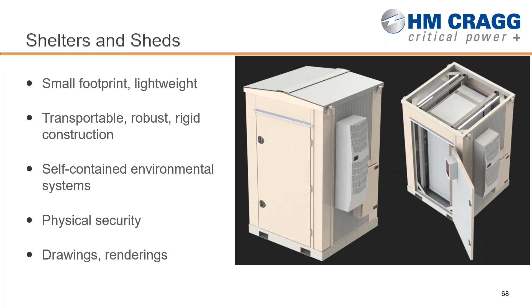Here's another example where we had everything in one cabinet: UPS, battery cabinet, automatic transfer switch, custom input and output distribution so we could plug in pin and sleeve, and redundant air conditioners built in, with Conex style doors. In this specific iteration, the customer required us to do a load test to make sure the dynamic loading on the enclosure would not distort the door, so you could operate it even if one corner was out of level. Super rigid construction, very heavy duty — a really interesting project we were involved with.